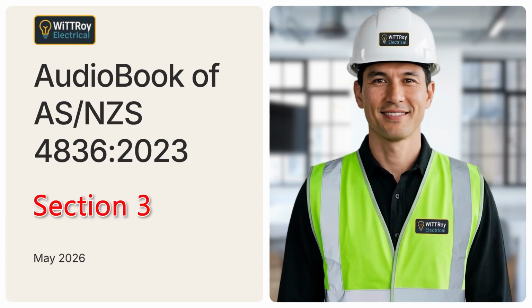Clause 3.1.1. Isolation principles. Clause 3.1.1 explains the basic isolation principles. Work must not be carried out on or near de-energized, exposed conductors or parts until a competent person has completed the required safety steps. First, the electrical equipment and conductors must be positively identified. The energy sources must also be identified. The isolation points must be identified.